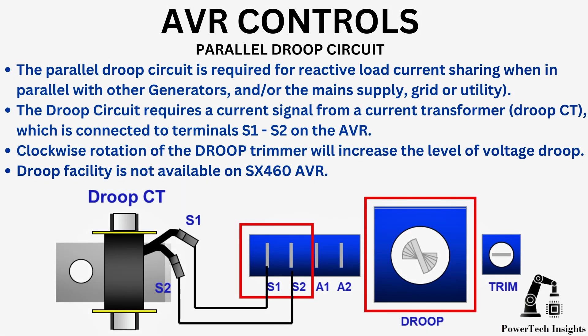AVR controls, parallel droop circuit. The parallel droop circuit is required for reactive load current sharing when in parallel with other generators and/or the main supply, grid, or utility. The droop circuit requires a current signal from a current transformer (droop CT), which is connected to terminals S1, S2 on the AVR. Clockwise rotation of the droop trimmer will increase the level of voltage droop. Droop facility is not available on SX460 AVR.